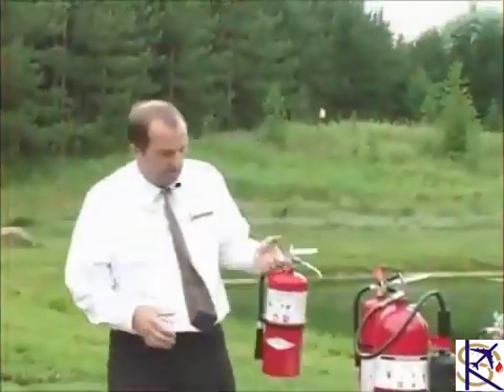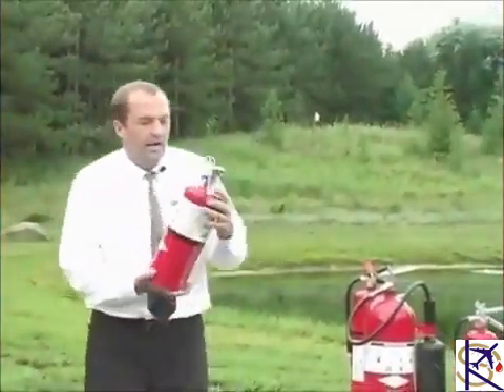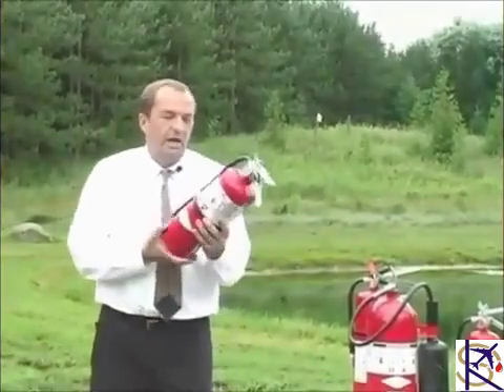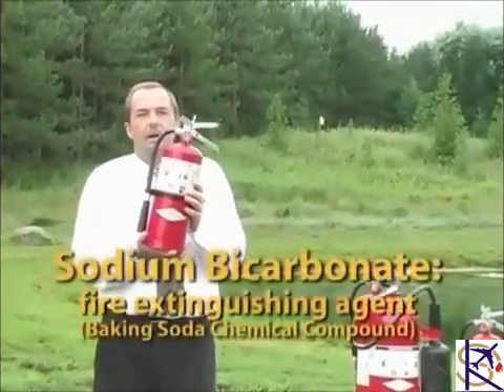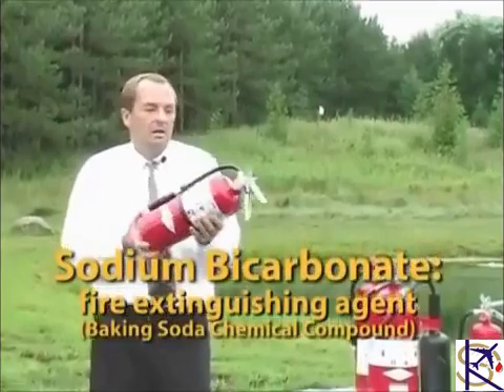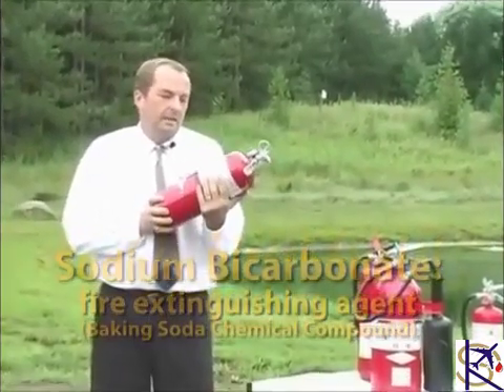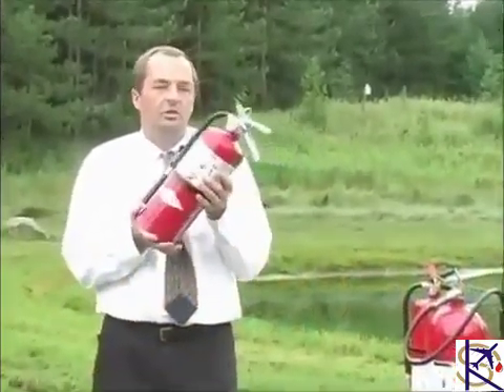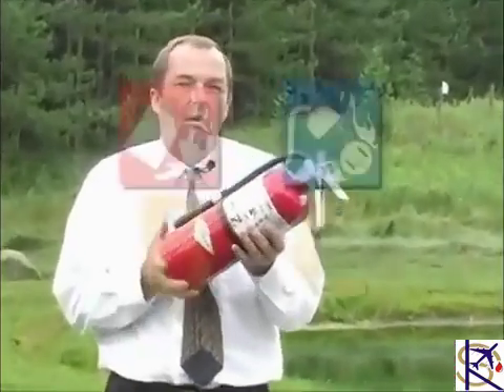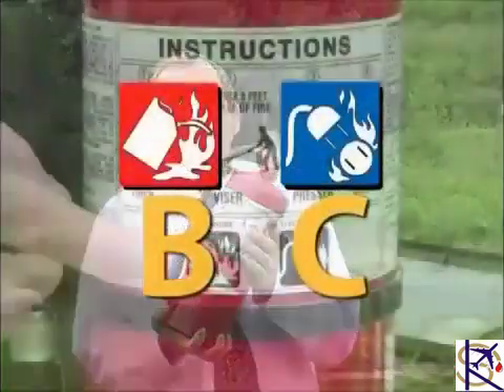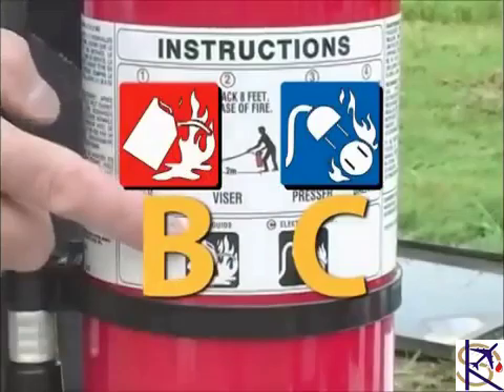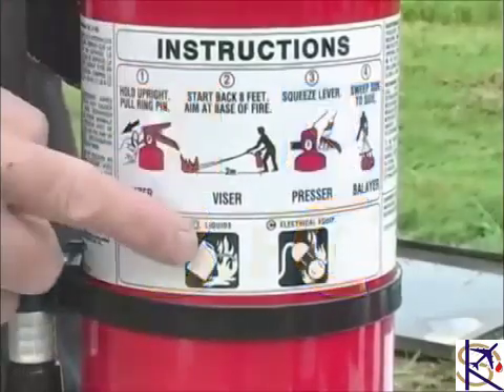Let's talk about the regular dry chemical. Regular dry chemical is simply bicarbonate of soda. It is primarily used in kitchens. It has no A rating at all. It is completely a B and C. It has a 40 BC rating.